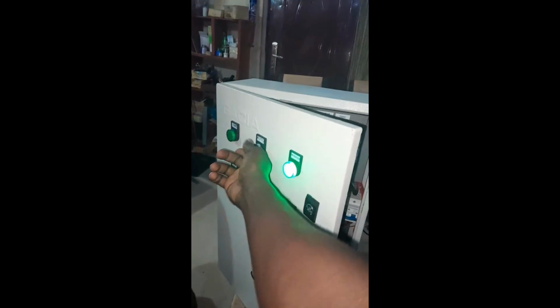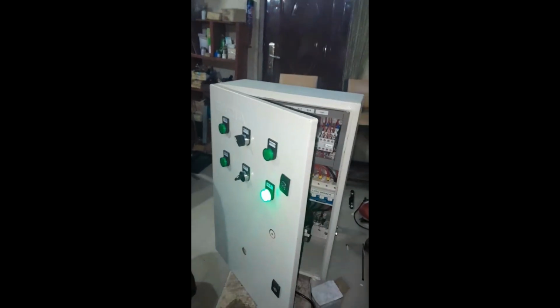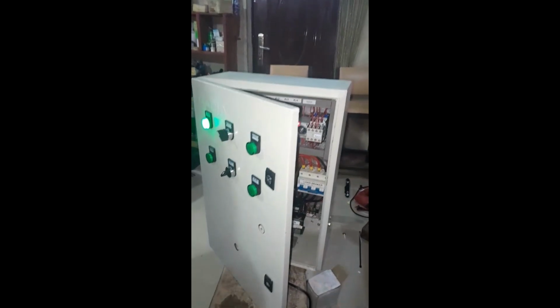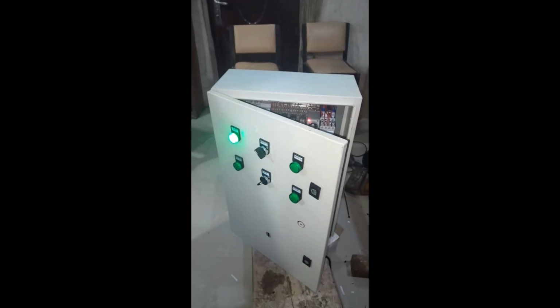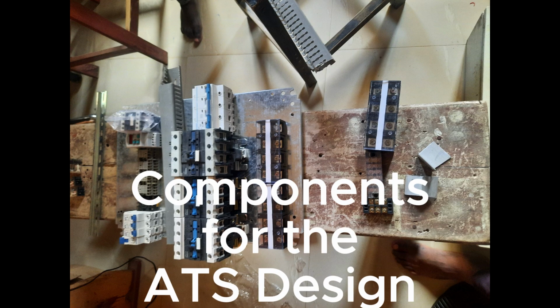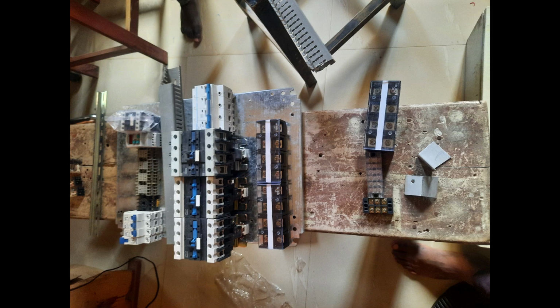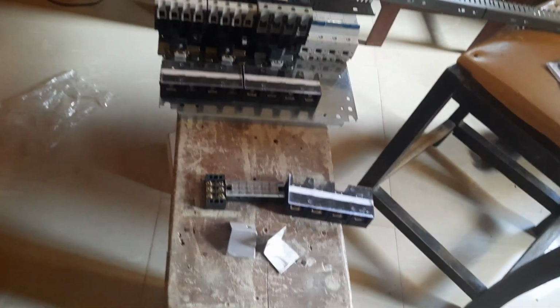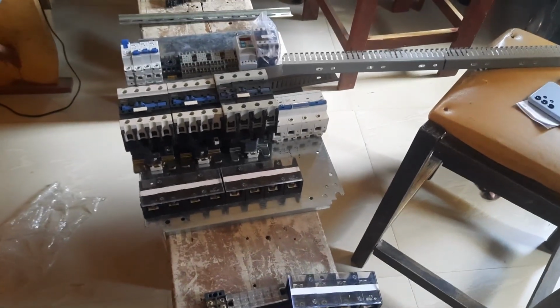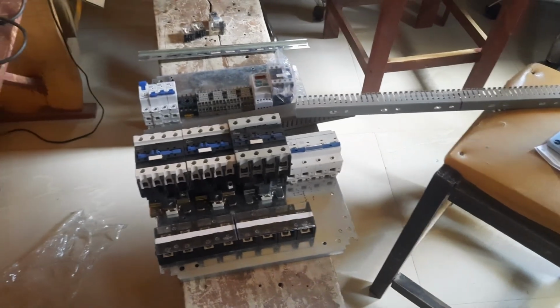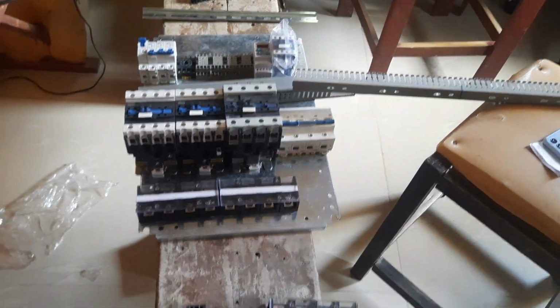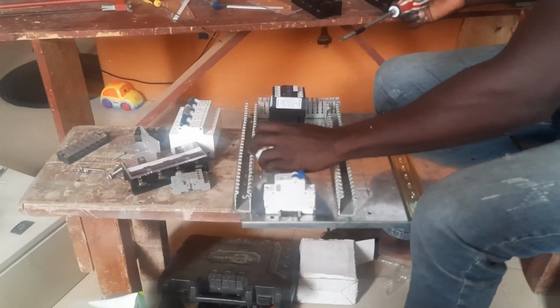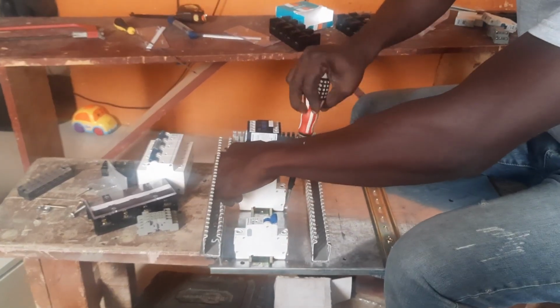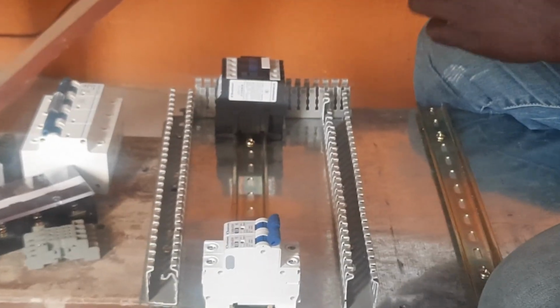To build a system this robust and smart, you can't cut corners. You need both muscle and brains. For the muscle, we used heavy-duty three-phase contactors, each rated for their specific source. A massive 120A contactor for the utility grid, as it carries the main load. 100A contactors for both the diesel generator and the solar inverter, and an 80A contactor is more than enough for the smaller fuel generator. For the brains, we integrated multifunction time relays to control the switching sequence and eliminate power transients, ensuring a smooth, safe transition every time.